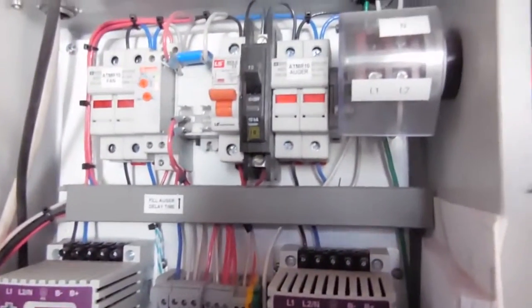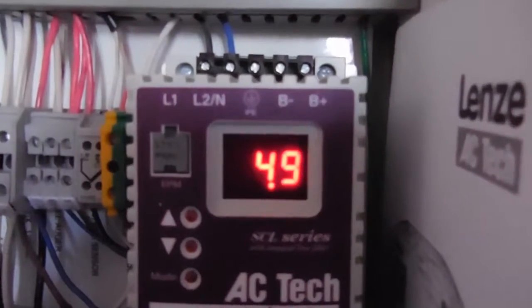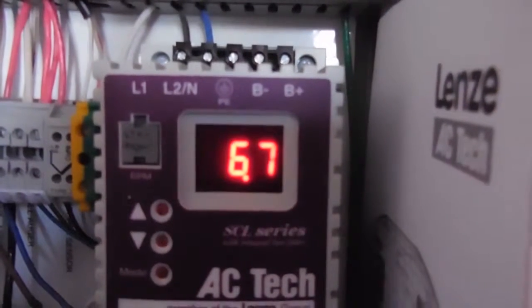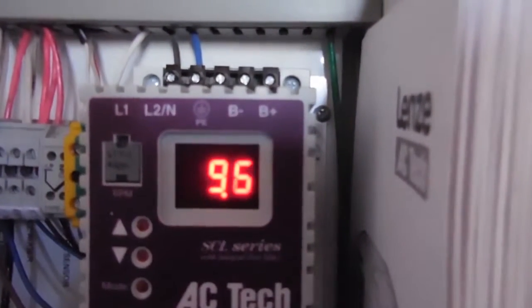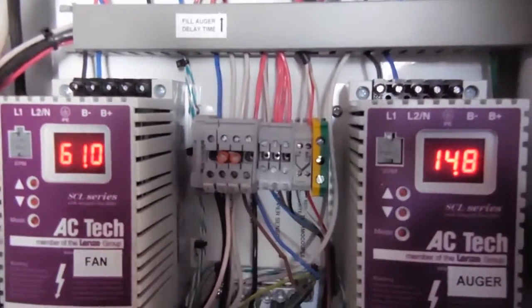...your feed speed increases — see that? It starts climbing. Your water temperature is falling, your firing rate starts increasing to try to compensate for the rate of temperature drop, which means increased heat demand. And as your temperature continues to fall, your feed rate continues to climb. Firing rate is increasing.